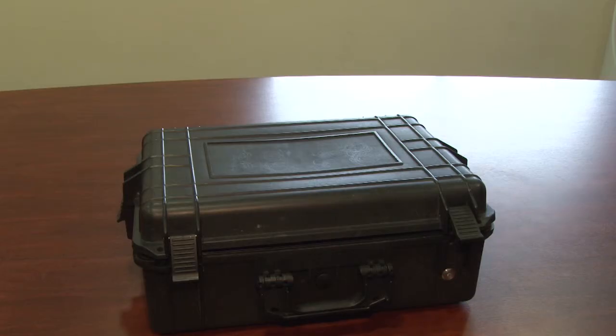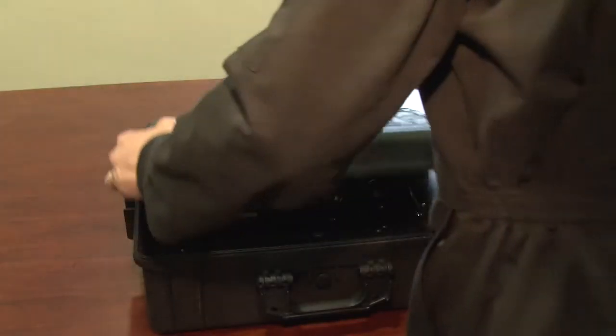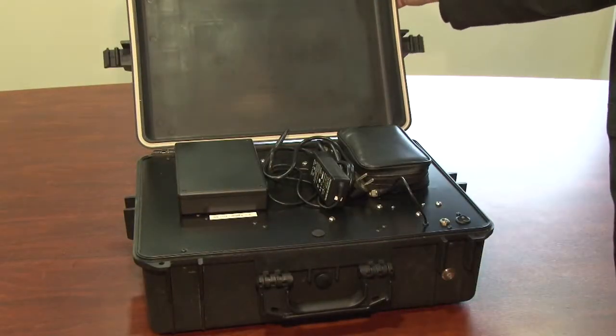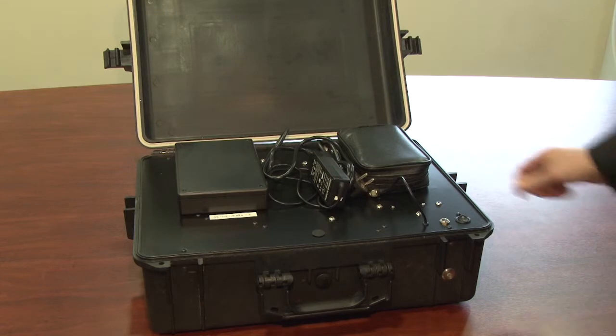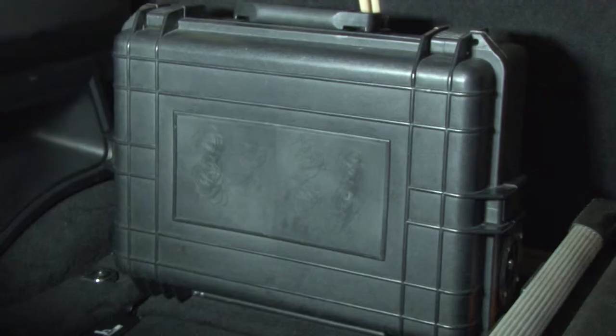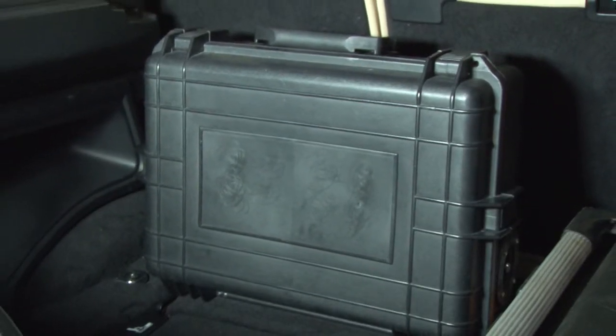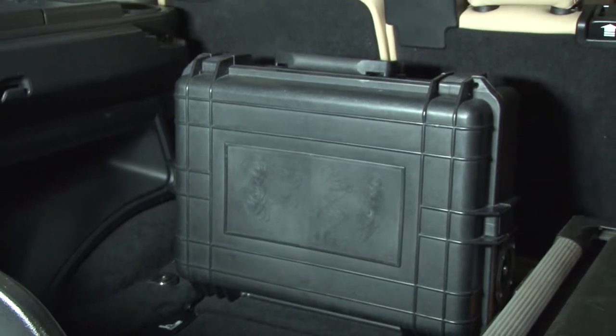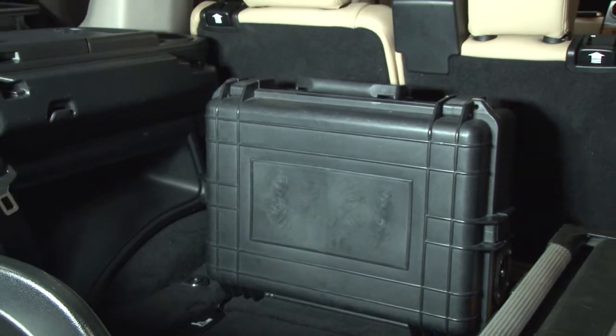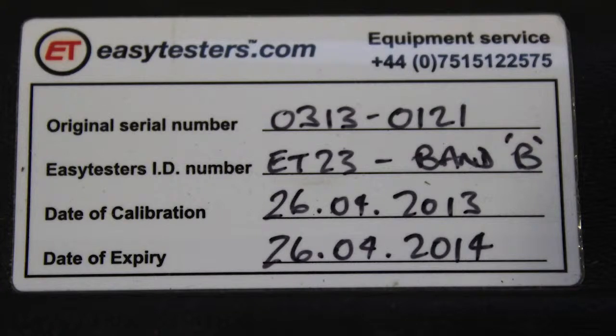All equipment required to carry out the test procedure, apart from the liquid side hoses and multi-fit adapters, is located inside the black box. When transporting, ensure that no sudden shocks are encountered, as this equipment is to be treated as fragile. The black box is labelled, showing the serial number, ID, calibration and expiry dates. Do not open the box in damp or wet areas.